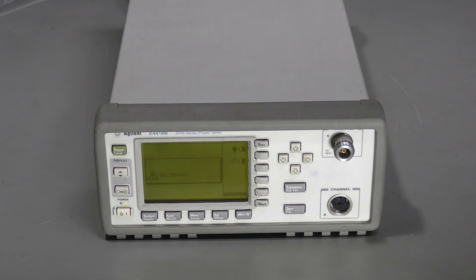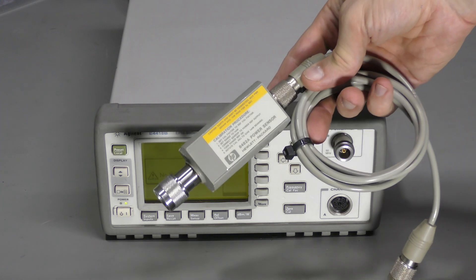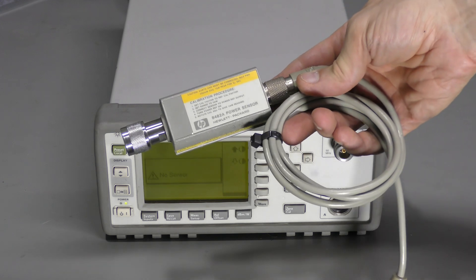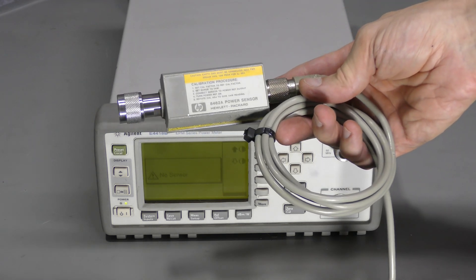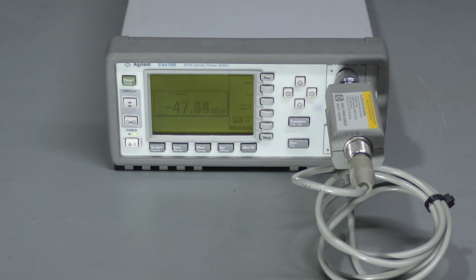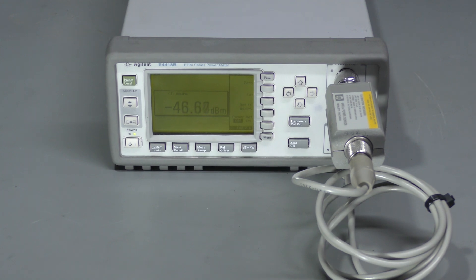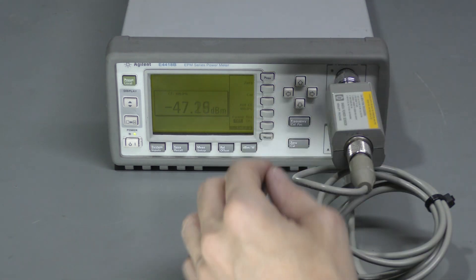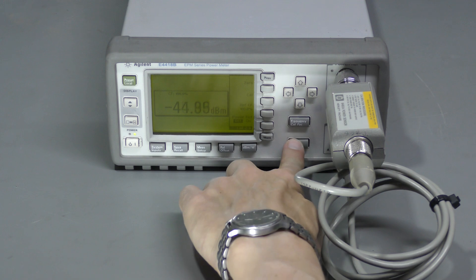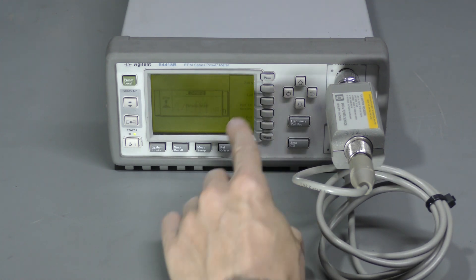And here I have a good old HP 8482A power sensor. Let's give it a go. The sensor is connected to the reference output. Let's calibrate it. First we do zero.